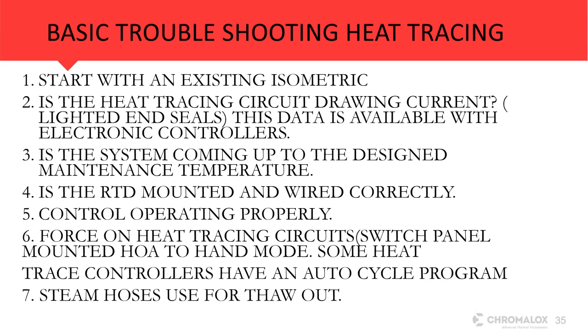You can force the heat tracing circuits on. If you have a switch panel that's mounted HOA, you can force that into hand mode. Some heat tracing controllers have an auto cycle program, so you can do that in early summer and figure out that your heat tracing is working. Or if you're in emergency mode, you can switch this thing to hand and turn everything on and then go do some checking.